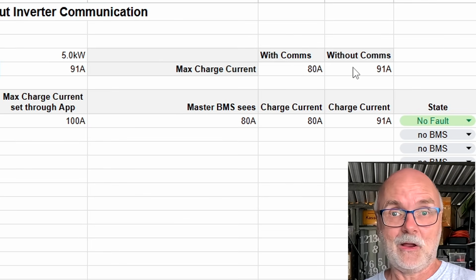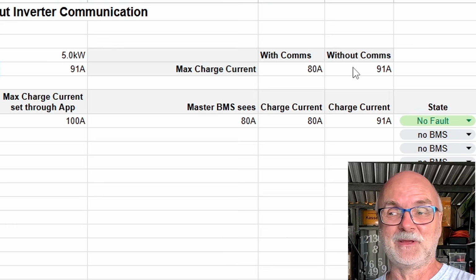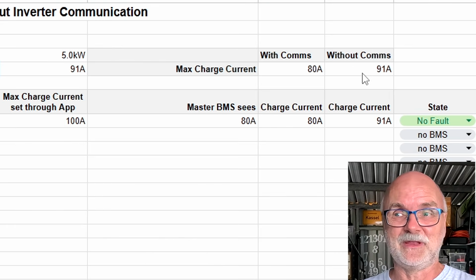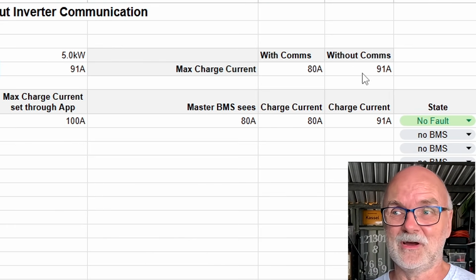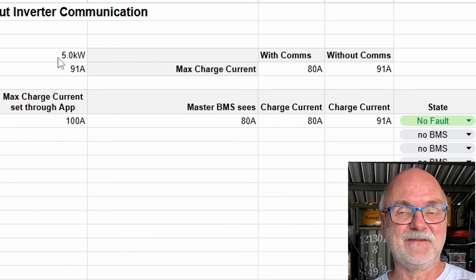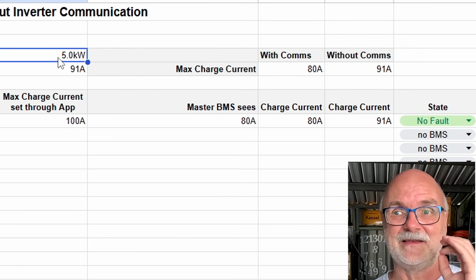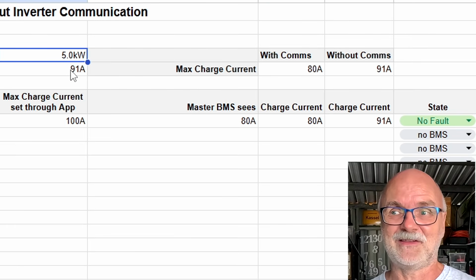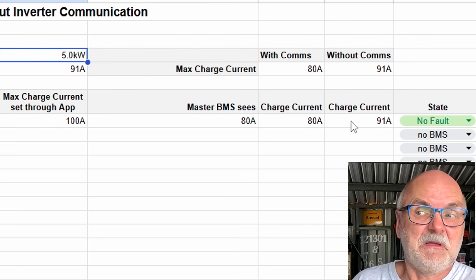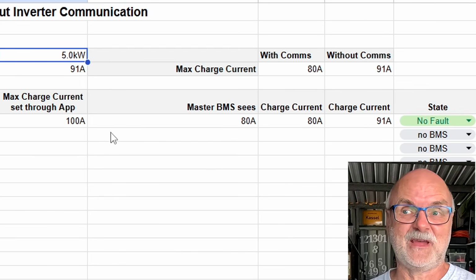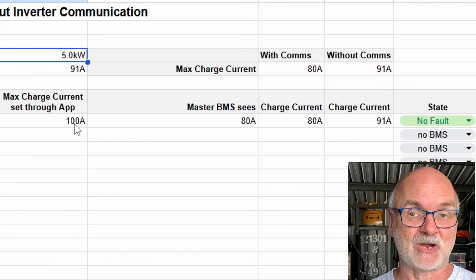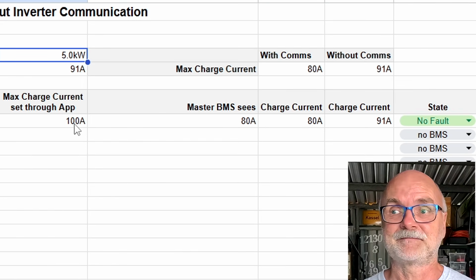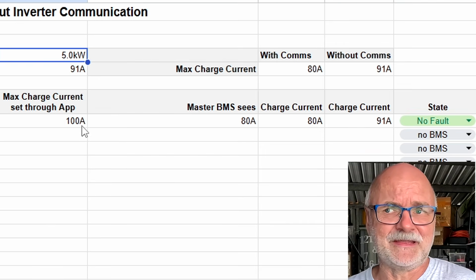only. Without communication, we will get the full 91 amps because there's no communication between your BMS and the inverter, it will just deliver whatever the sun shines outside. Maximum power, 91 amps. Still, it is in the safe path because you have set 100 amps of maximum charge current in your BMS. So how do you choose the correct charge current in your BMS here?